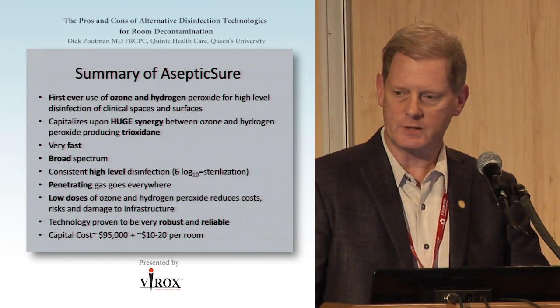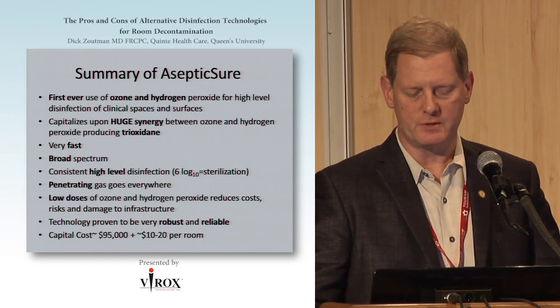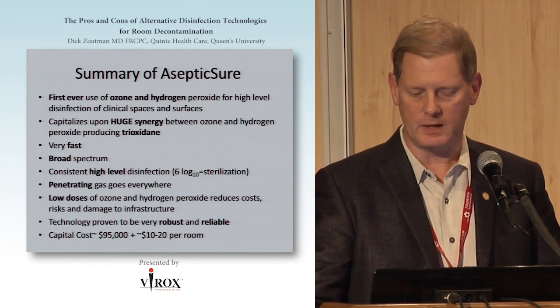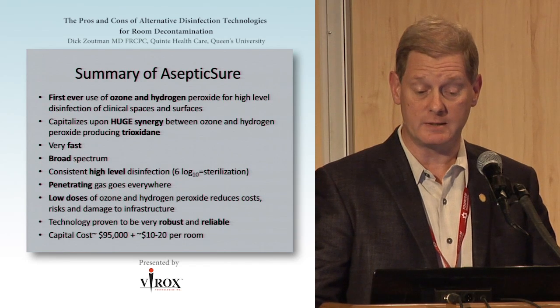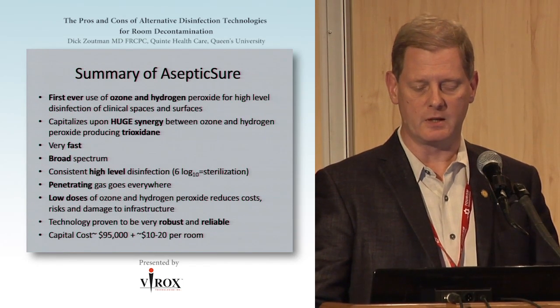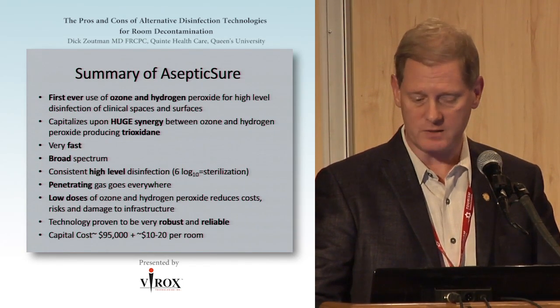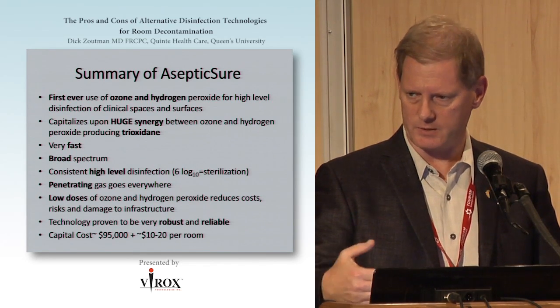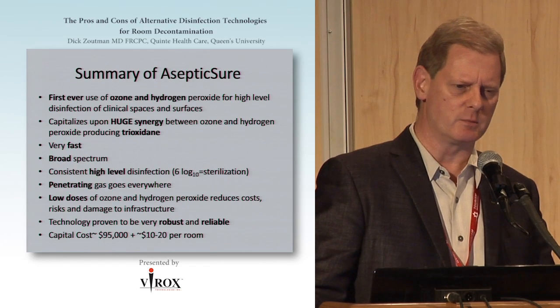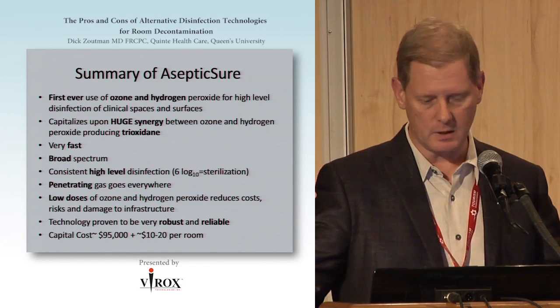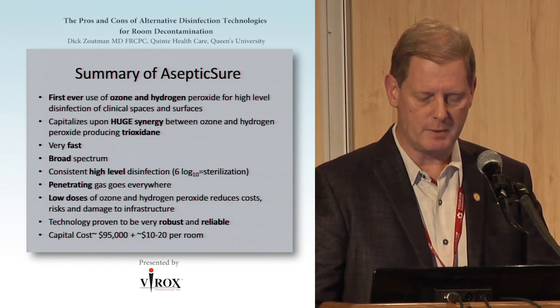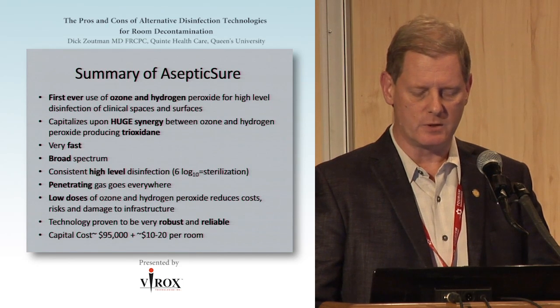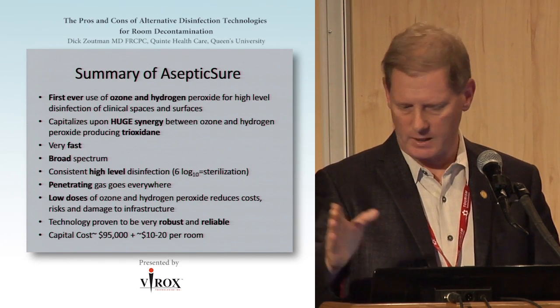So we're very excited about this because it's really the first demonstration of a combination of techniques using ozone and hydrogen peroxide together with a very significant synergy. It's very fast. It takes about 20 minutes to ramp up the room. The exposure times are, as I showed you, and about 20 minutes to bring it back down, depending obviously on the size of the room. Very broad spectrum, and the gas, of course, penetrates, and you don't have line of sight issues.